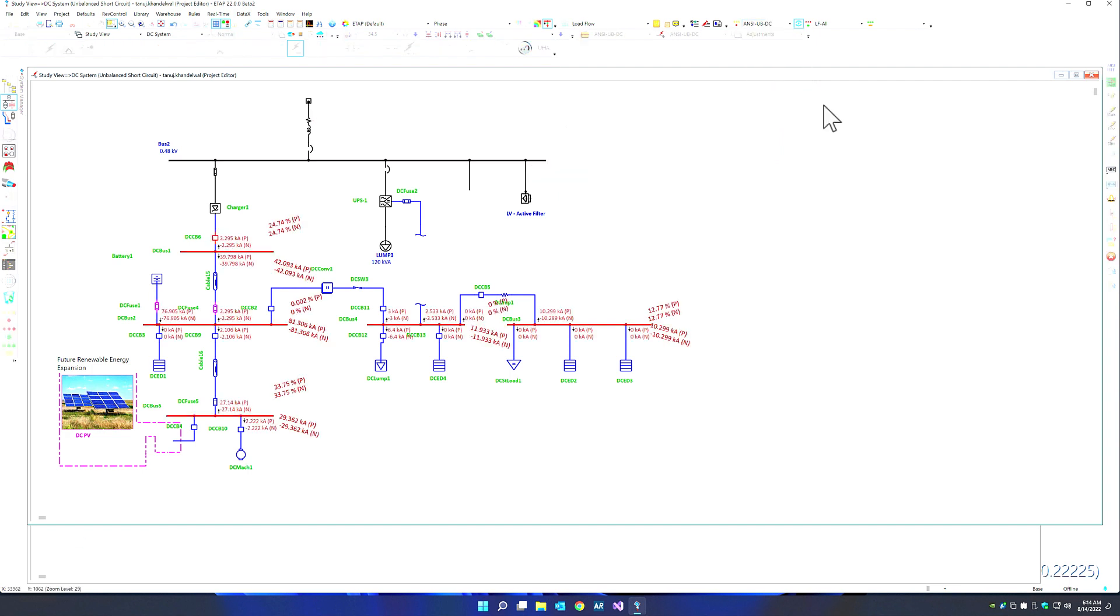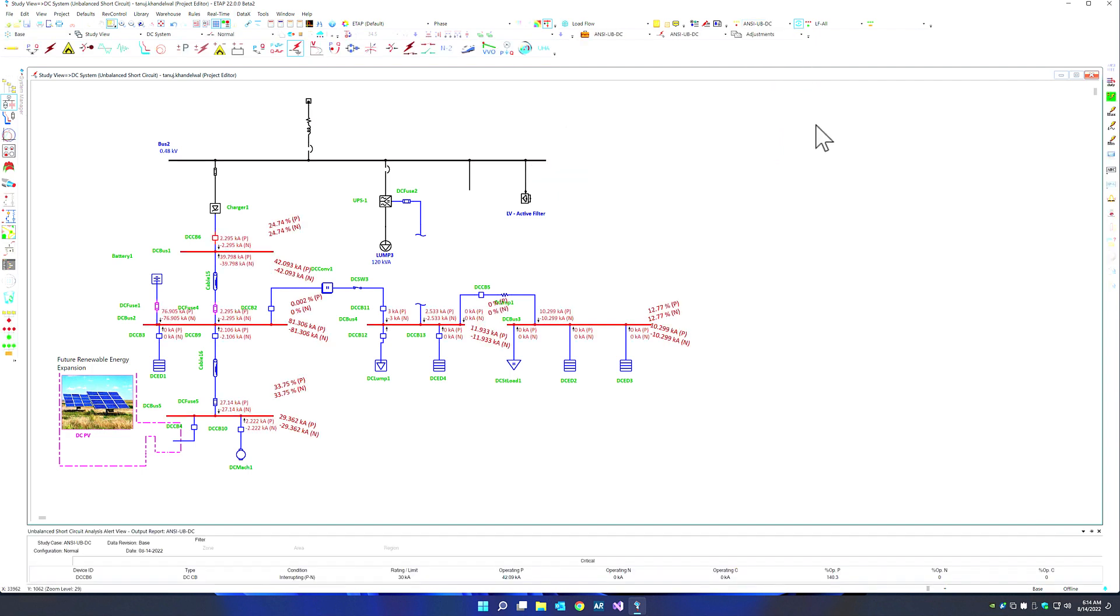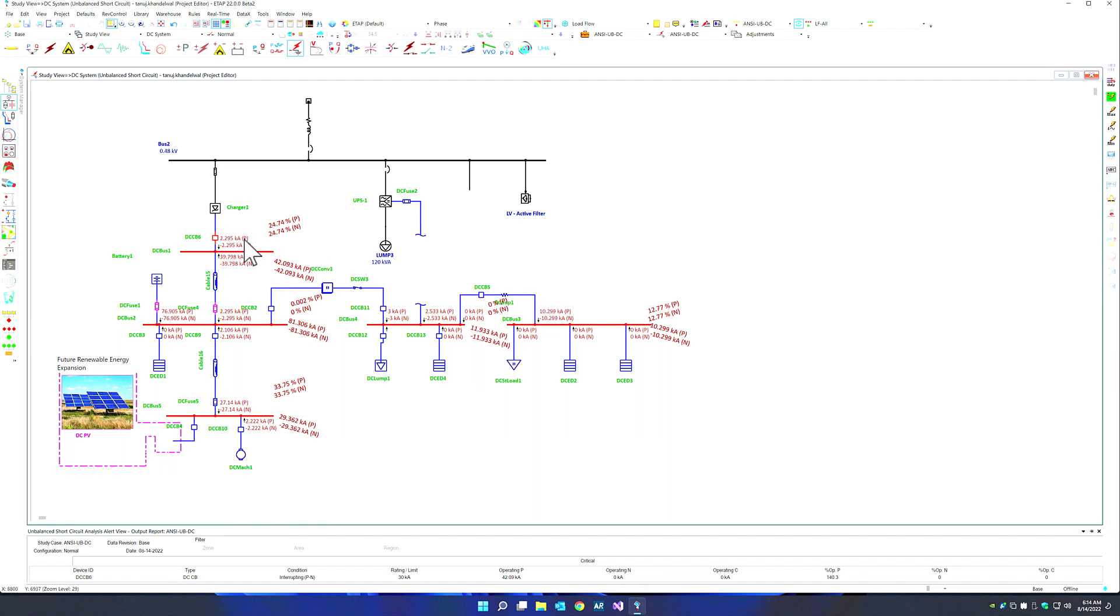In order to evaluate our DC short circuit, we can simply run our DC scenario here. You can see the short circuit simulation on the DC network, which is shown in blue, based on IEC 61660. We can see the contribution, which is the forward current and the return current in our DC network, along with the phase contribution values and the voltages as well.